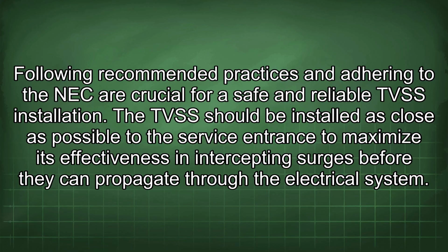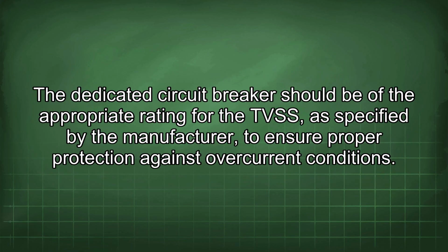The TVSS should be installed as close as possible to the service entrance to maximize its effectiveness in intercepting surges before they can propagate through the electrical system. The dedicated circuit breaker should be of the appropriate rating for the TVSS as specified by the manufacturer to ensure proper protection against overcurrent conditions.